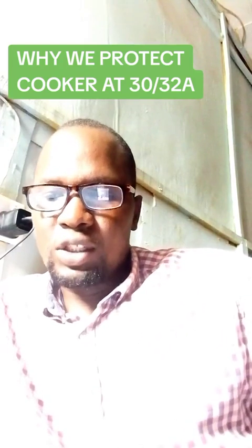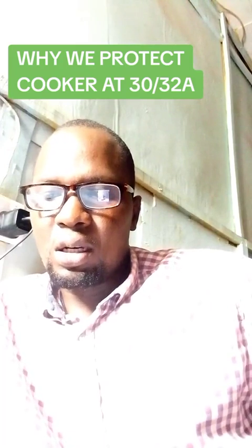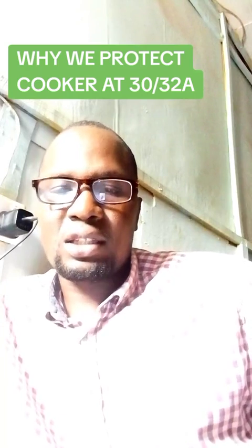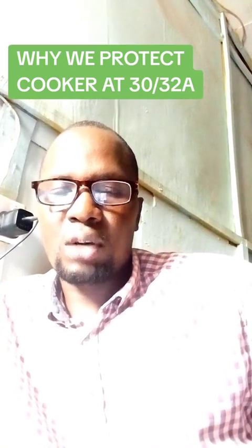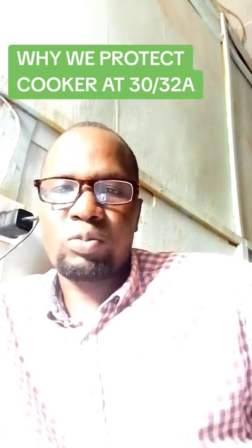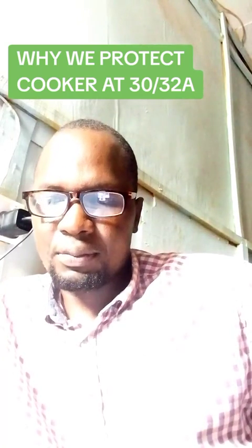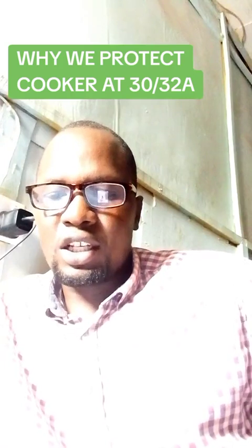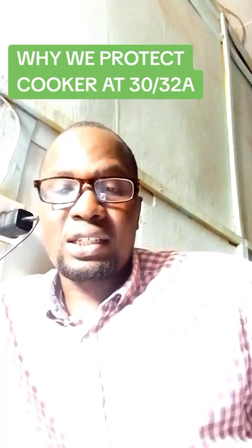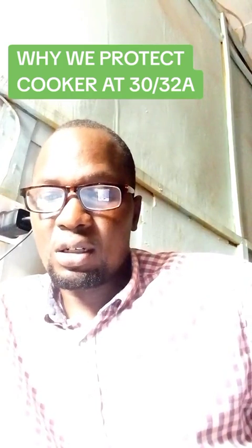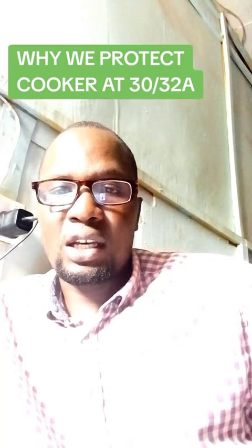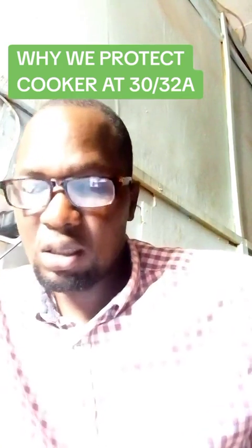Today we want to determine why we protect a cooker at 30 or 32 amps, or at a circuit breaker rated 30 or 32 amps. And this we shall realize just by calculating the current rating of an electric cooker as given on its specification plate.